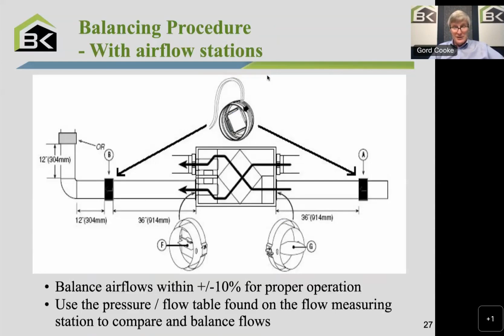And if it's not the same, then there are typically balancing dampers. You'll notice built into the collars of the unit, that F and G down at the bottom. Those are balancing dampers built into the collars of the unit. Sometimes it's a damper in the duct itself, sometimes on the unit, and you would simply balance it to within about 10%. So if it's 100 CFM of exhaust, we'd want 90 to 110 CFM of supply. That's about as accurate as you need to be. Don't need to be too worried about much worse than that.